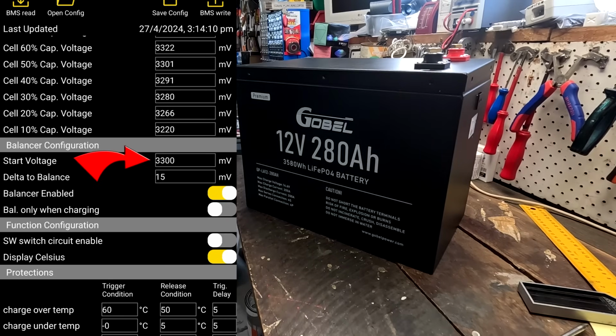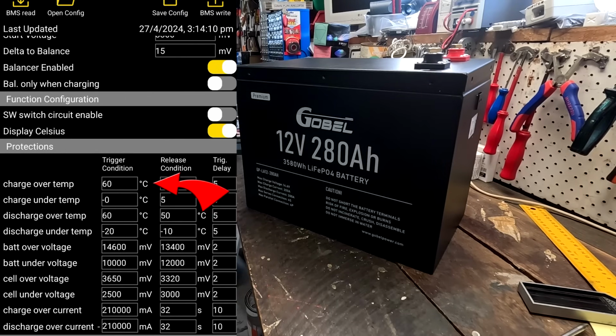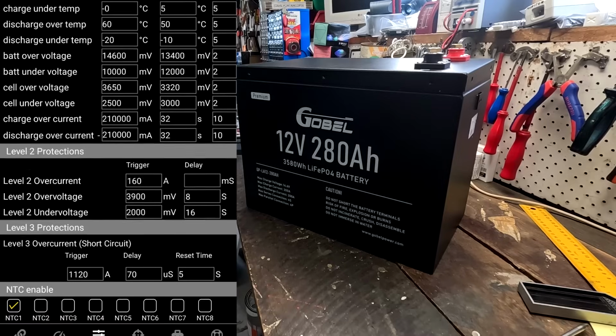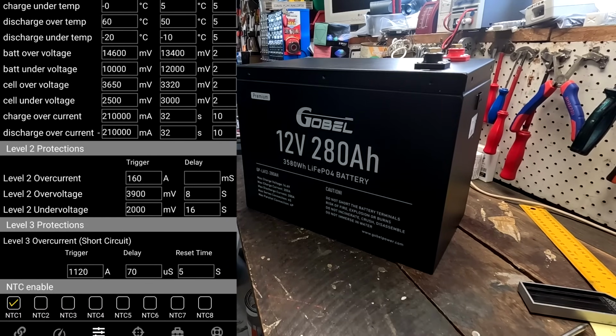Well, not really actually, but the charge balancer is turned off, which is good. What do we have here? Over temperature 60, charge under temperature 0 degrees. Nice. Battery over voltage 14.6 - this is for the whole battery. Not really interesting. Cell over voltage 3.65, under voltage 2.5. Charge 210, discharge 210 amps as well. And down here is the short current protection of 1120 amps for 70 microseconds.